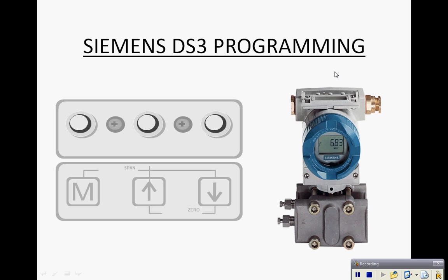The Siemens DS3 pressure transmitter has three magnetically coupled push buttons that sit under a lid on top of the transmitter housing. The button to the far left is the mode button which we can toggle through the 14 modes of operation of the transmitter, and the buttons to the right are the span and zero adjustments.